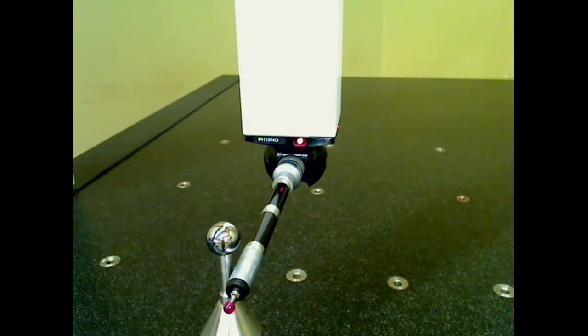You'll notice that the probe is up against the calibration artifact. The next thing I'm going to do is lock the x-axis on the CMM.